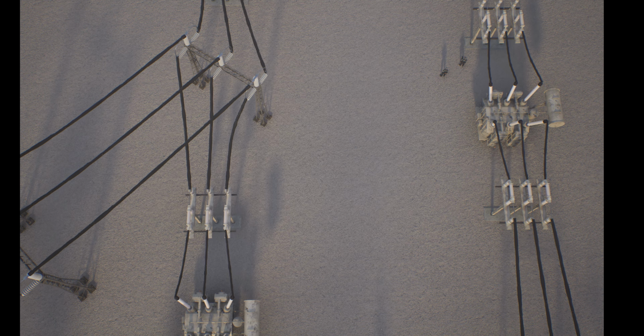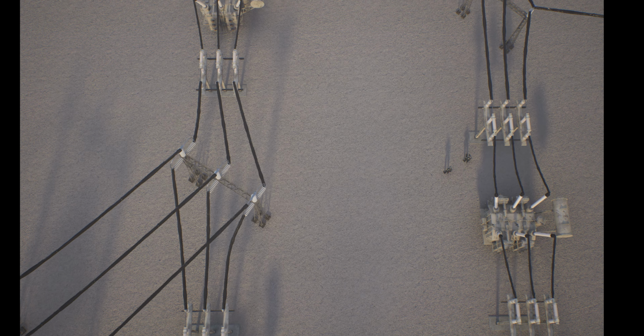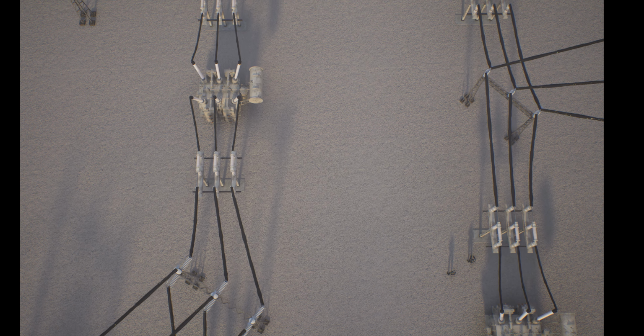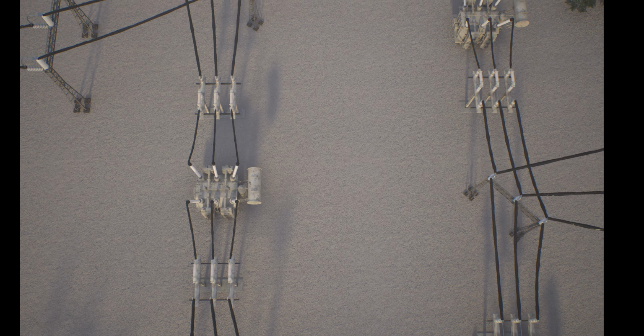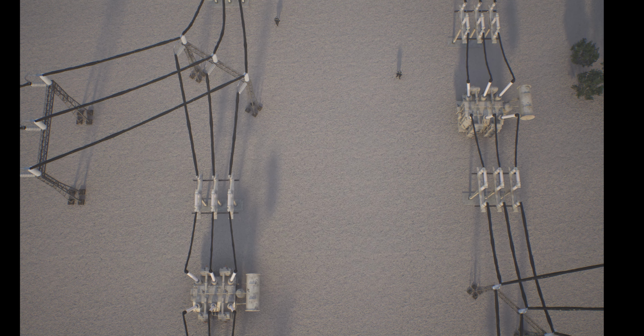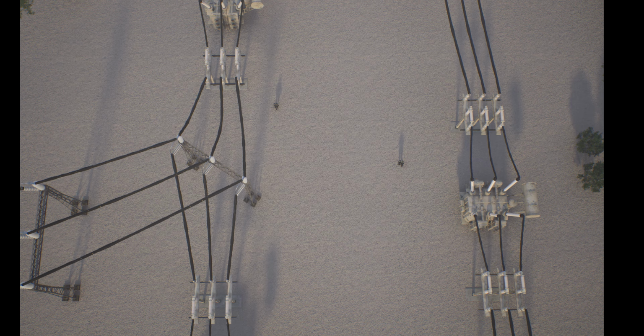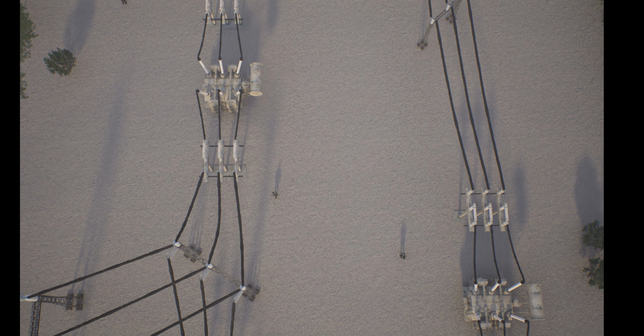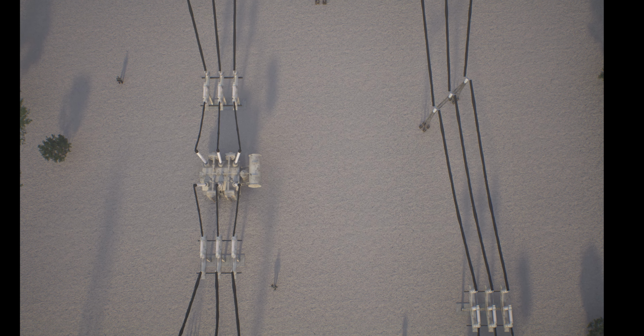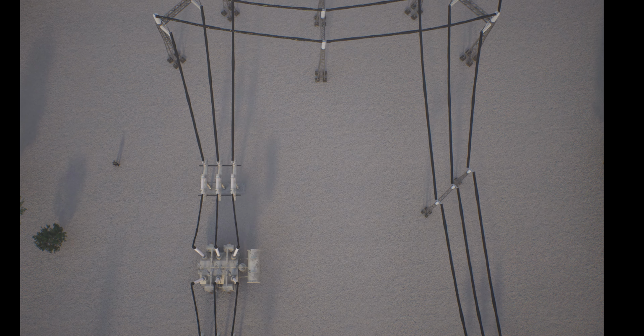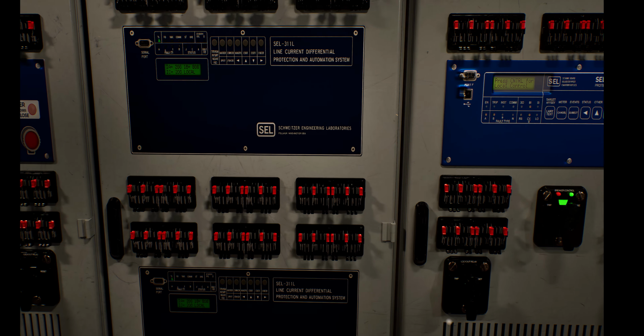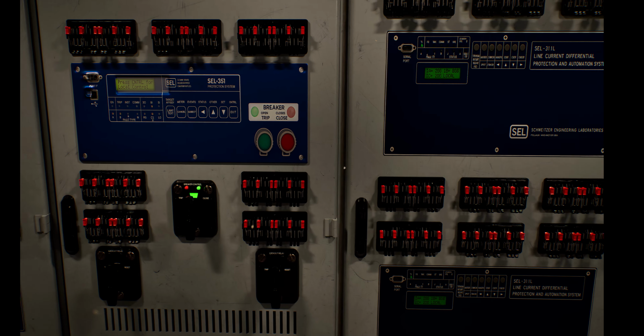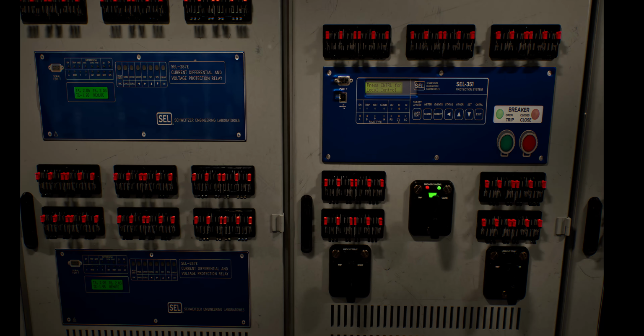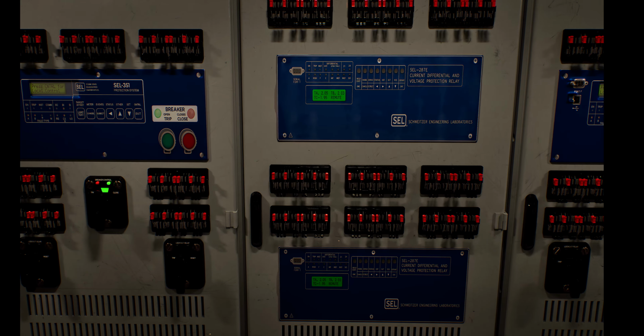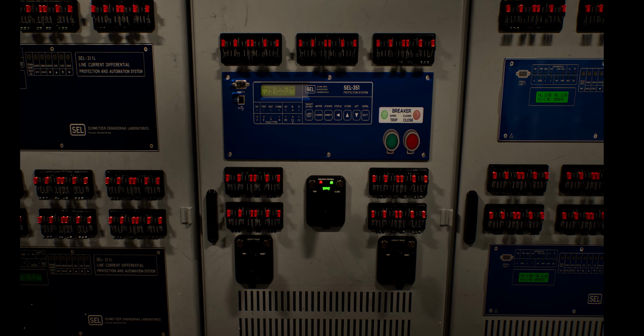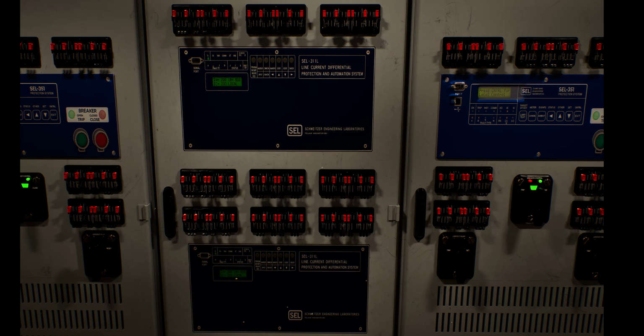All work must follow approved job plans, job hazard analyses, and switching orders. NFPA 70E requires a documented risk assessment before work begins, including identification of shock and arc flash hazards. No task is so urgent that it justifies unsafe behavior. In general, we do not work in substations that are undergoing construction. The number of hazards present during construction activity is significantly higher.